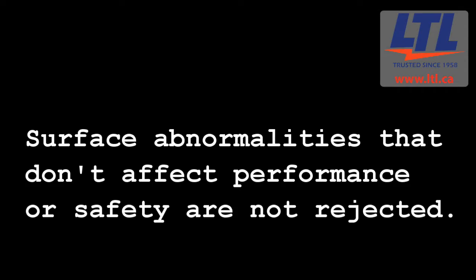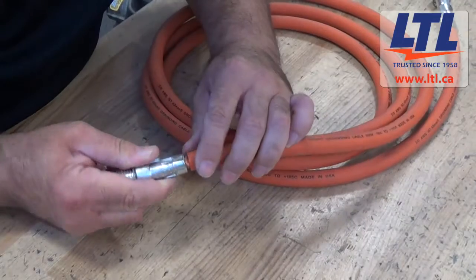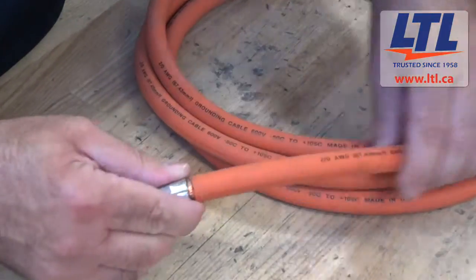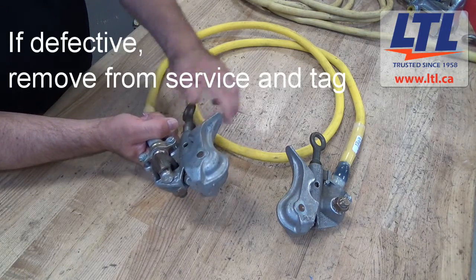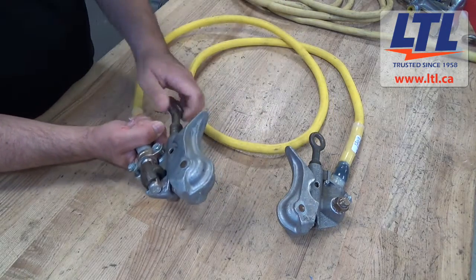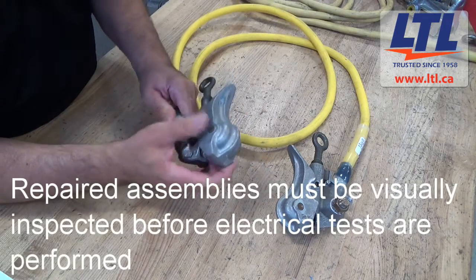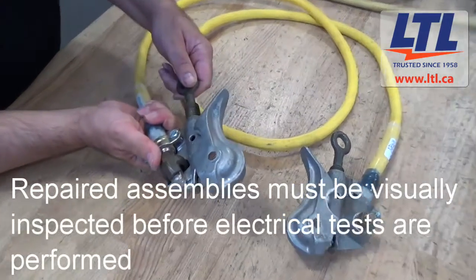Surface abnormalities that don't affect part performance are not a cause for rejection. We inspect the jumpers for cracked or broken ferrules or clamps, and check all physical connections for tightness. If a grounding jumper assembly is found defective, it shall be removed from service and tagged. A grounding jumper assembly that was repaired must be visually inspected once all repairs are complete before any electrical tests are performed.